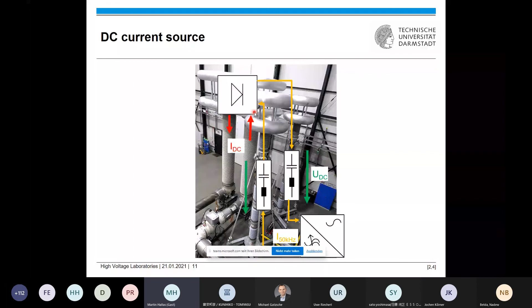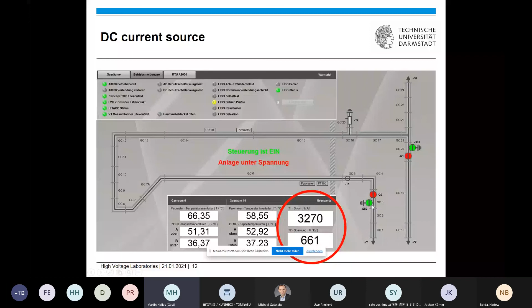And this high frequency AC current can then be used to feed a rectifier at high voltage potential, and this rectifier then generates the high DC current inside the test loop. And that this is actually really working, you see here in this picture. We have injected a current of 3,200 amps at a potential of 660 kV. So this concept is really working, and you can inject a high DC current at a high DC voltage.